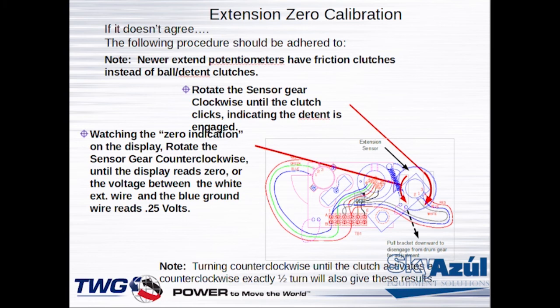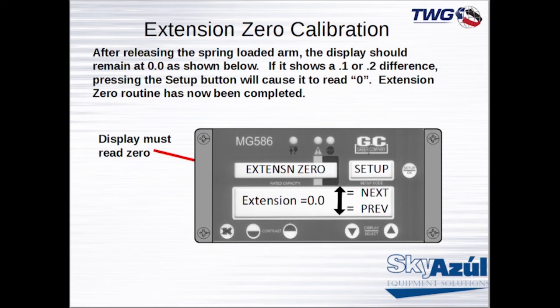Go to the terminal strip, measure between the blue and the white wire, and make sure you can get this 1/4 volt. Now the reason you have the 1/4 volt is so that the computer sees some kind of voltage pattern and knows that the cable hasn't been broken and reeled back and shut the sensor clear off. So if the sensor's at 0, the system doesn't recognize 0. It's gonna drop into dash lines and say, well, we've got an A04 here. You're gonna get an error code. So you have to have that little 1/4 volt gap in there.